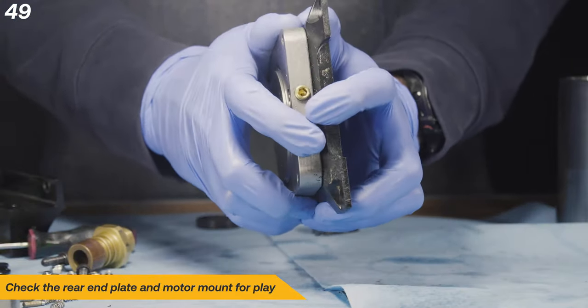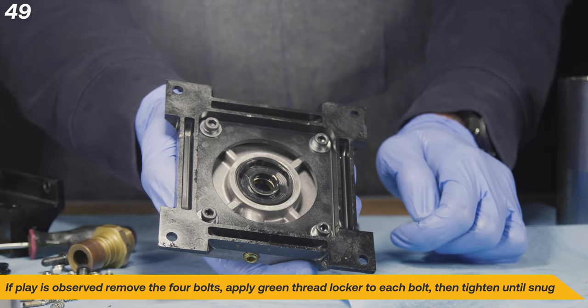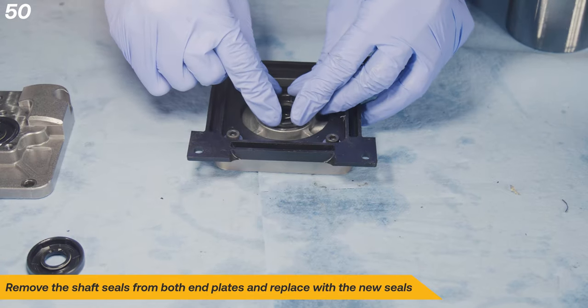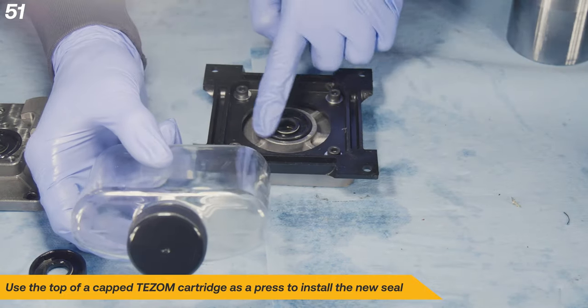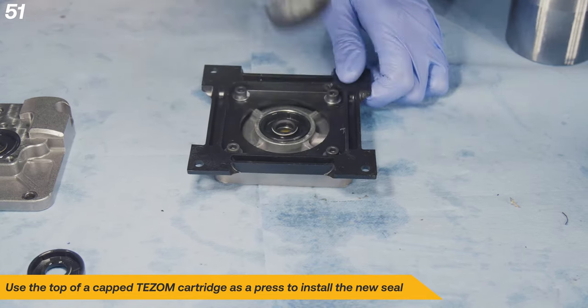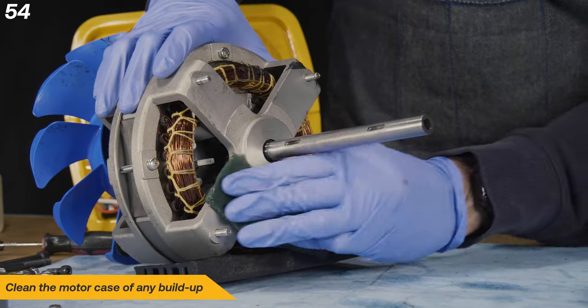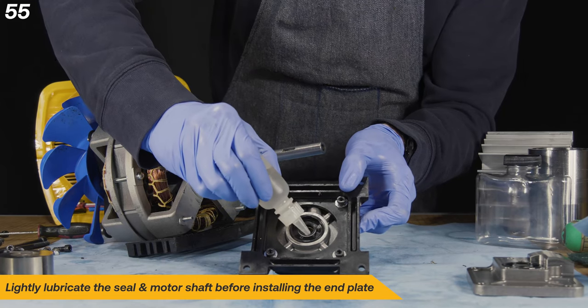Check the rear end plate and motor mount for play. If play is observed, remove the four bolts, apply green threadlocker to each bolt, then tighten until snug. Remove the shaft seals from both end plates and replace with the new seals. Use the top of a capped TEZOM cartridge as a press to install the new seal. Make sure you apply even, firm pressure on the seal. Repeat this for the front plate. Clean the shaft of any debris before mounting the rear end plate. Clean the motor case of any buildup. Lightly lubricate the seal and motor shaft before installing the end plate.